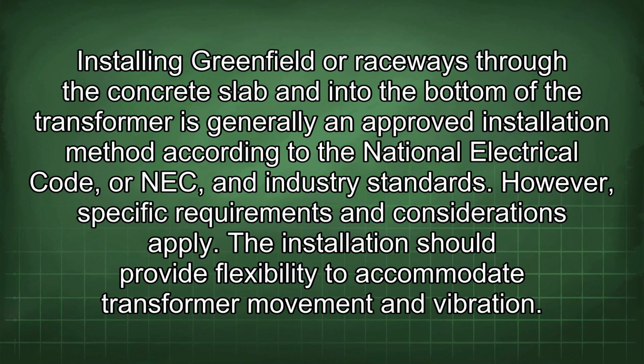Installing greenfield or raceways through the concrete slab and into the bottom of the transformer is generally an approved installation method according to the National Electrical Code, or NEC, and industry standards. However, specific requirements and considerations apply. The installation should provide flexibility to accommodate transformer movement and vibration.